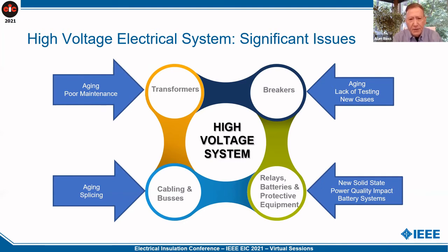And of those 100,000 transformers every year, 64% of them have excess IEEE standard moisture, 64%. And it's killing the insulation.